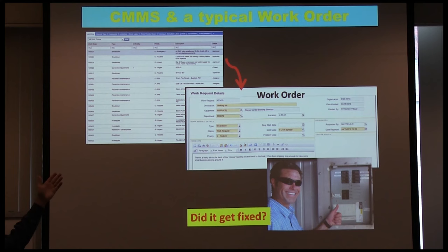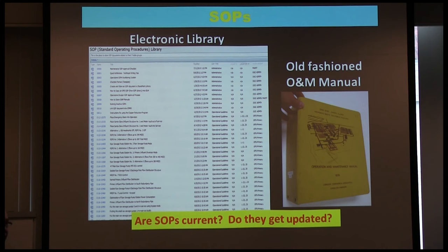This is where you need your CMMS operator available during inspection day — you'll pull up the files and show the work order was submitted, then go out to the power panel or wherever to show the problem was actually corrected. I've had inspections where they went to that level of detail — 'I want to see the actual panel, the relay that was replaced.' Nothing scarier than taking that walk out there hoping they fixed it. Nothing more satisfying than arriving and seeing that they did.